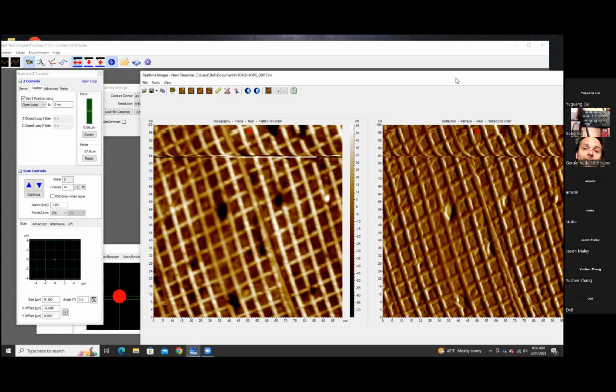I think when you switch it in, you actually disconnect and inject the signal. So I'm going to switch everything to out, and then you have X plus, X minus, Z, Y plus, Y minus. I'm going to measure one at a time. So measure X plus, reading. Let me see. Should I put it on 200 volts at range, right? You don't want to short the voltmeter. My meter auto adjusts, so I don't typically look at that. But yeah, make sure that your range is appropriate.